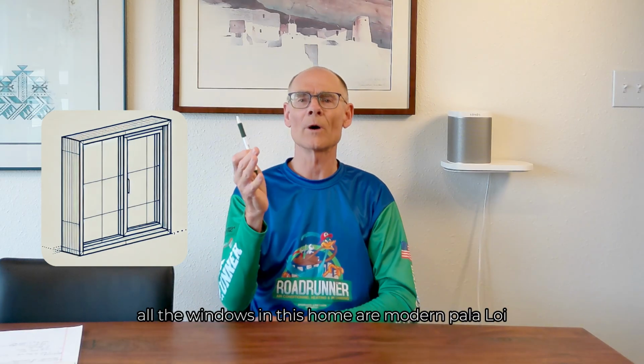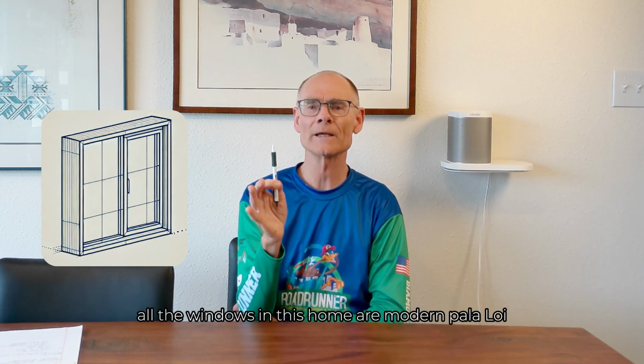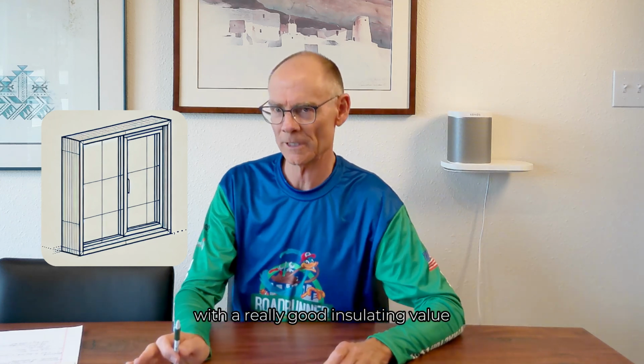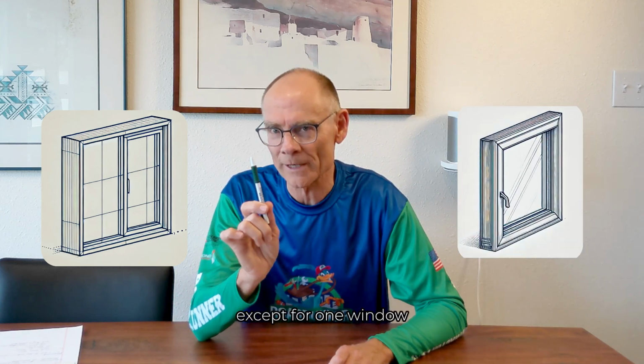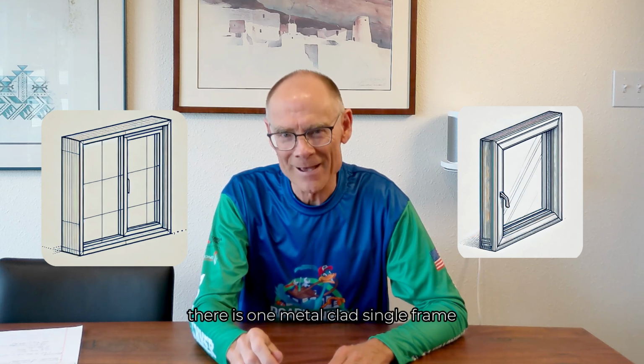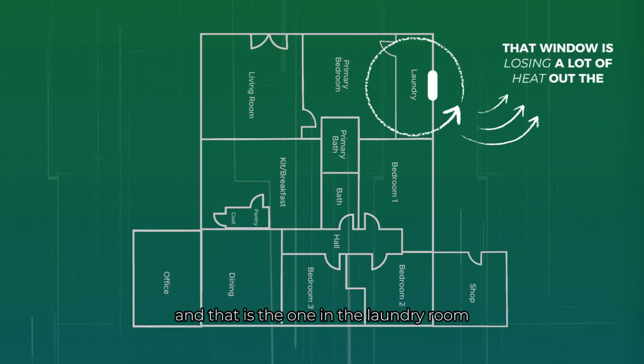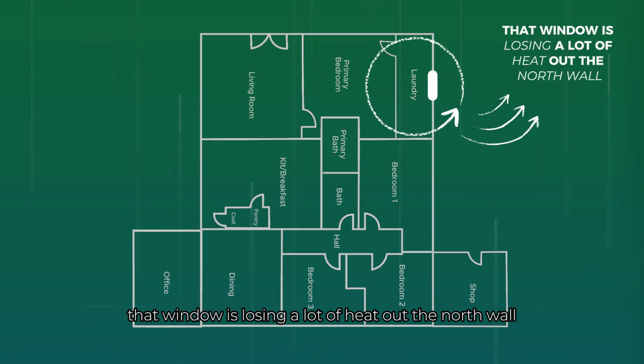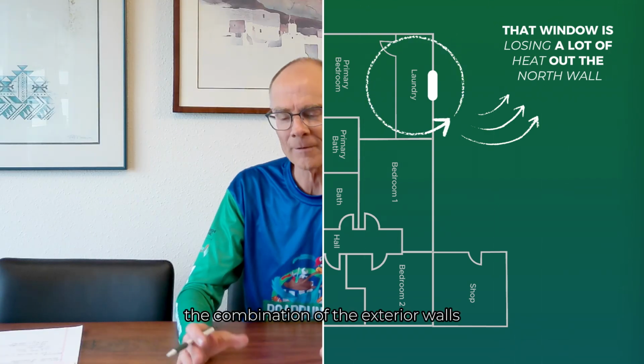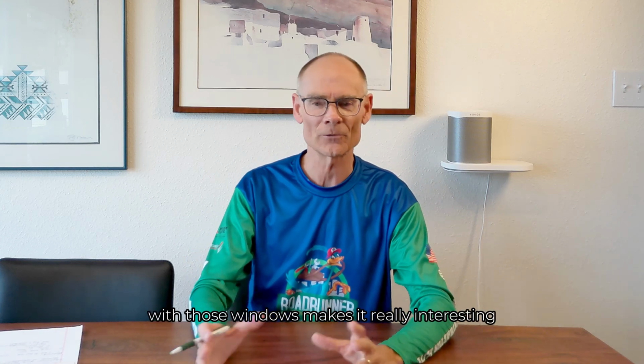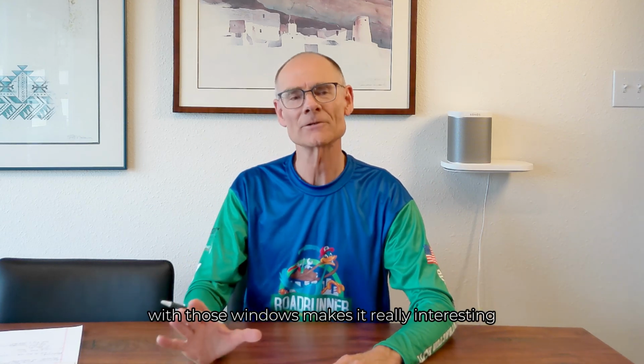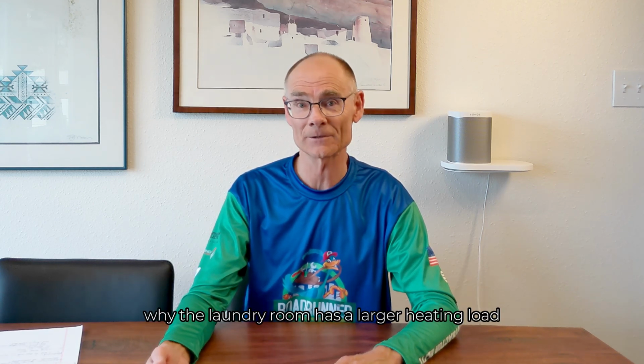All the windows in this home are modern Pella low-E clad wood windows. So, outstanding windows with a really good insulating value, except for one window. There is one metal-clad single pane window, and that is the one in the laundry room. That window is losing a lot of heat out the north wall. The combination of the exterior walls with those windows makes it really interesting, but actually explainable, why the laundry room has a larger heating load than the kitchen breakfast room.